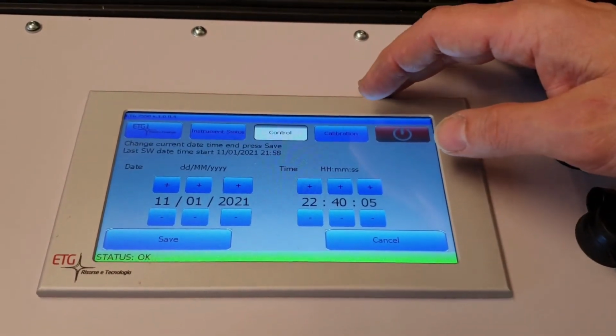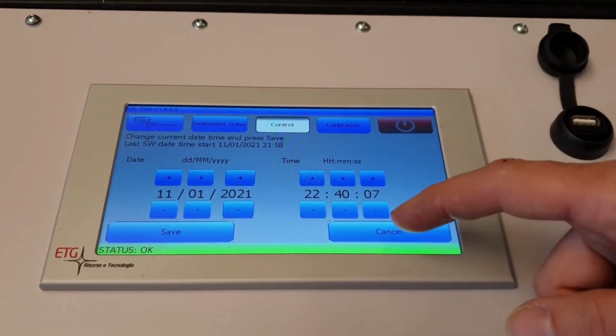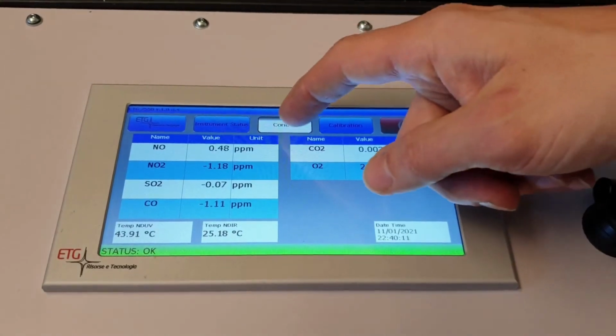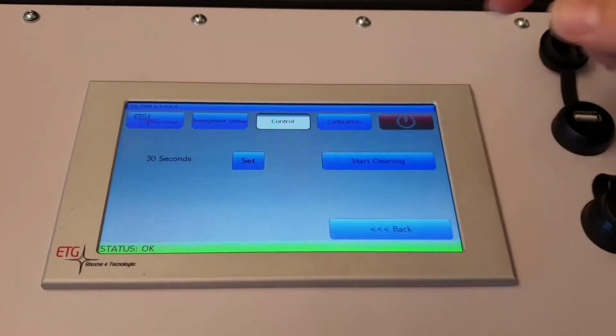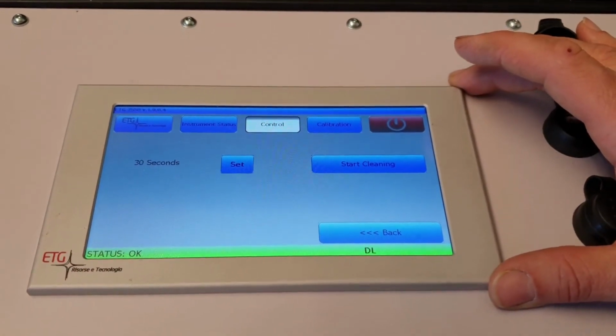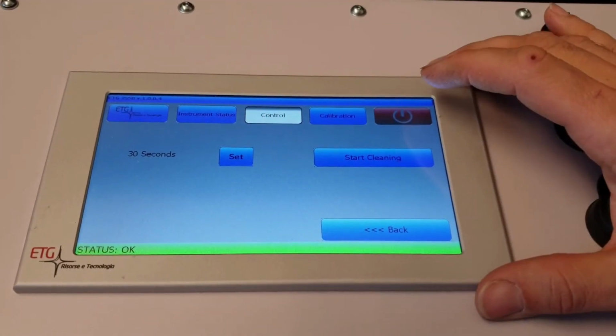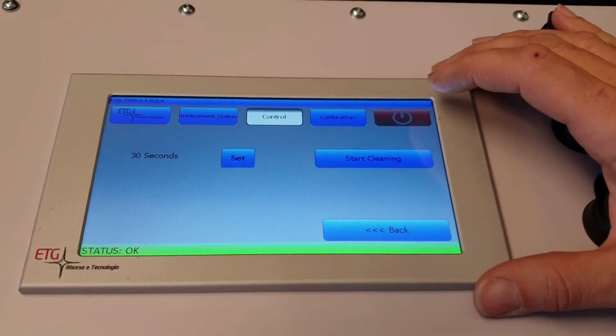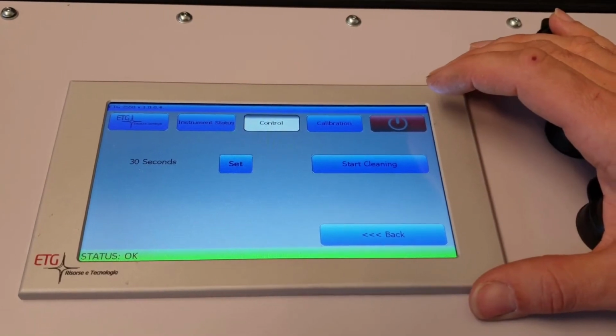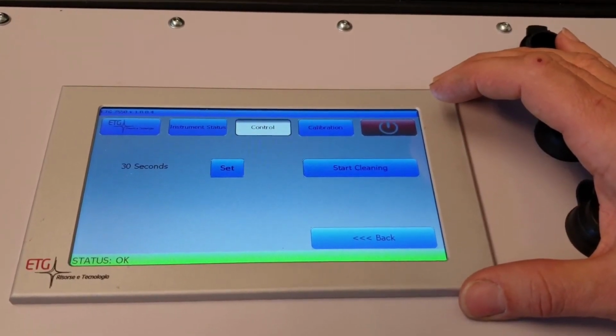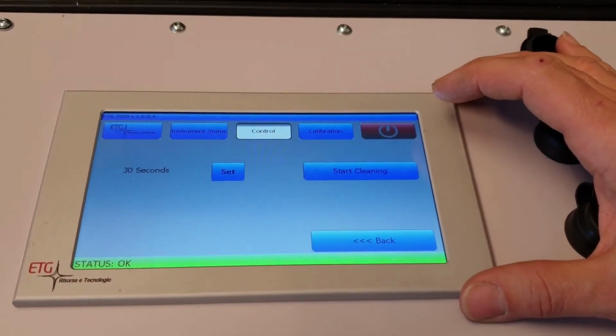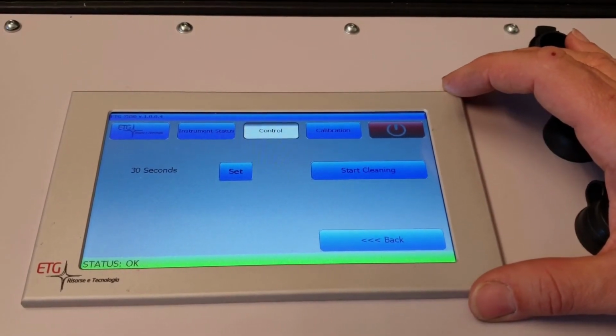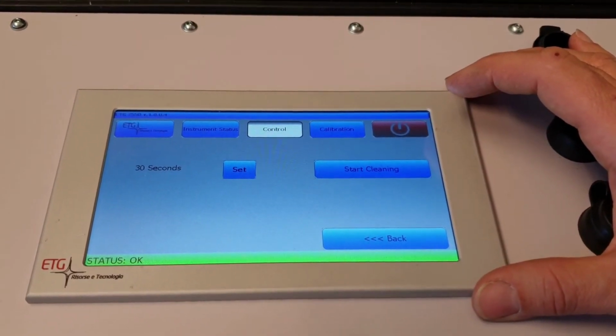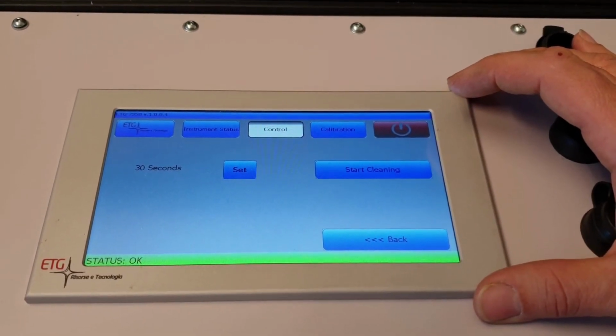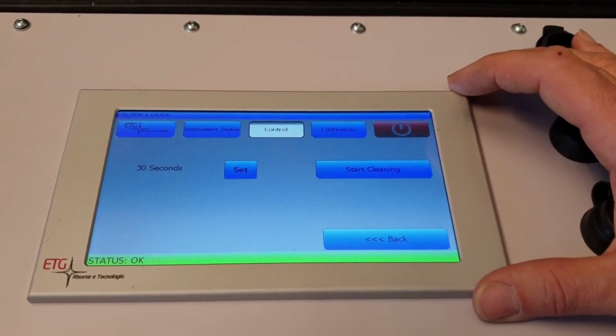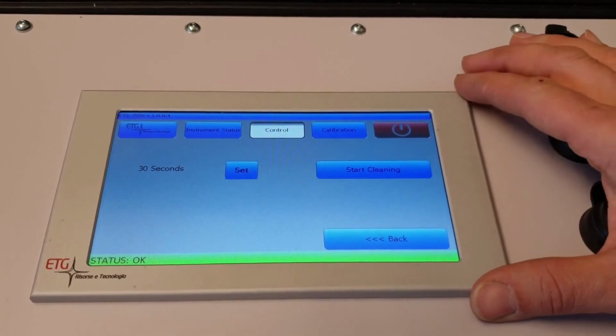Set date and time. And start the cleaning function. It's mandatory to do the cleaning procedure when you have finished the sampling. You start the cleaning procedure this way, so that no corrosive gas stays inside the analyzer.